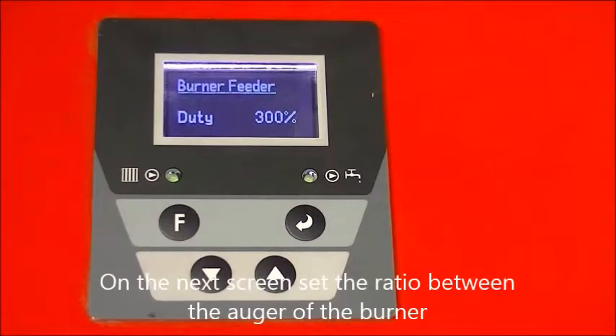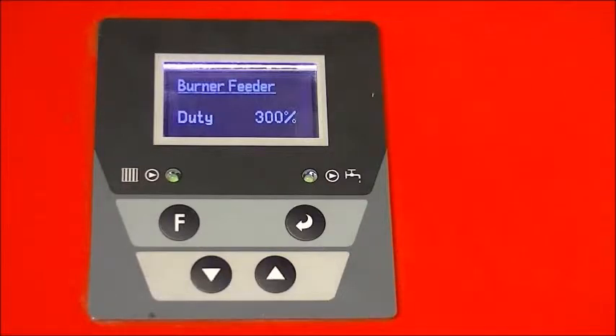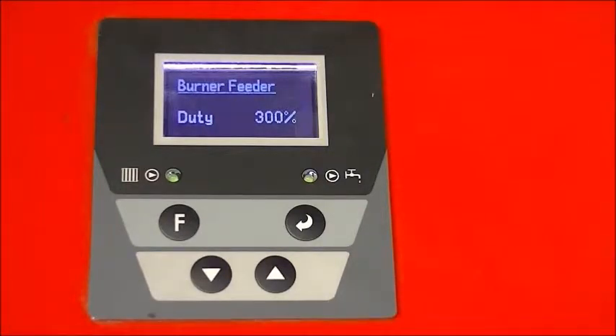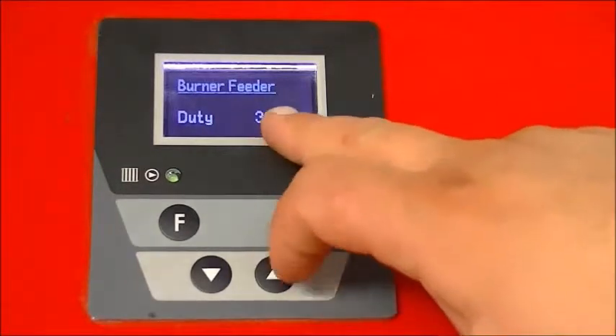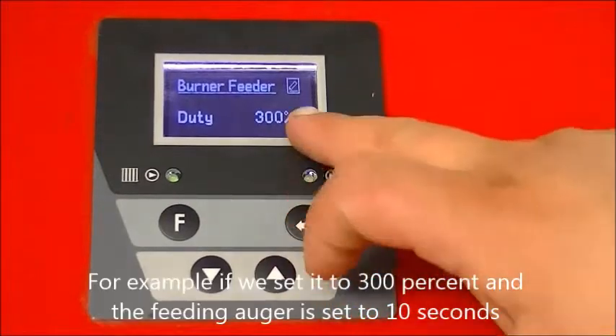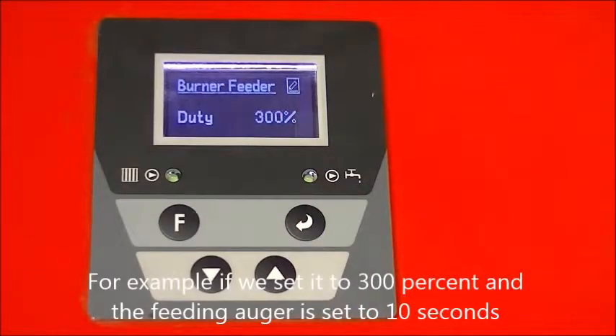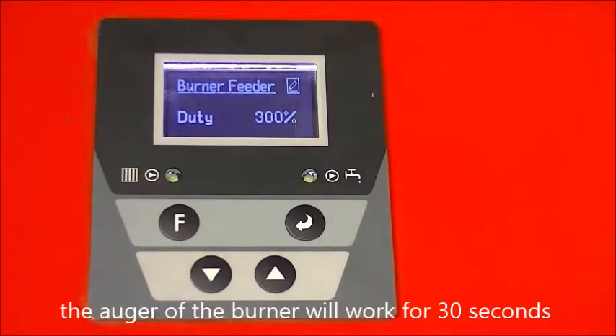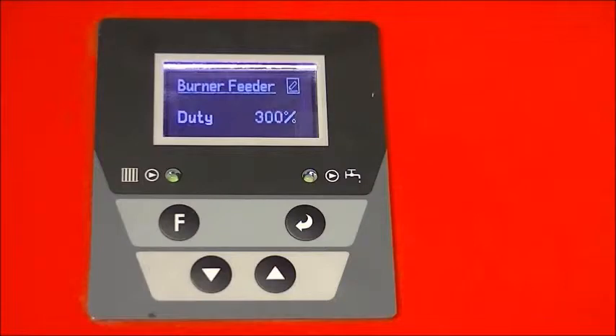On the next screen set the ratio between the auger of the burner and the external feeding auger. For example if we set it to 300% and the feeding auger is set to 10 seconds, the auger of the burner will work for 30 seconds.